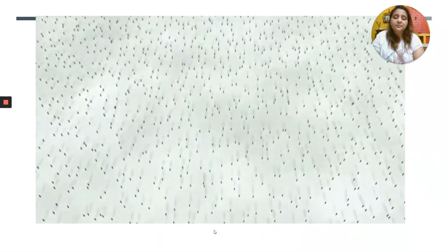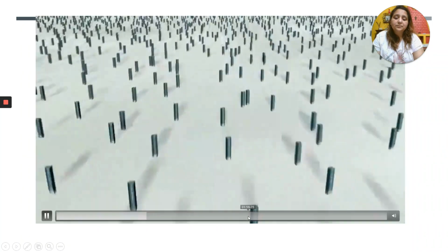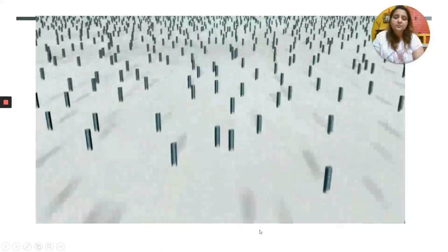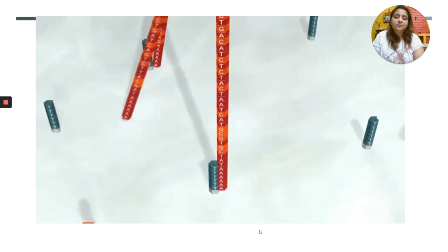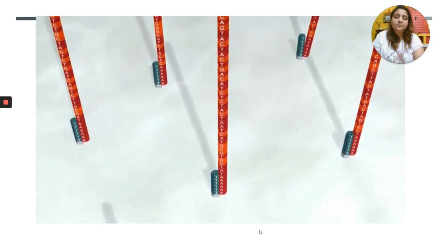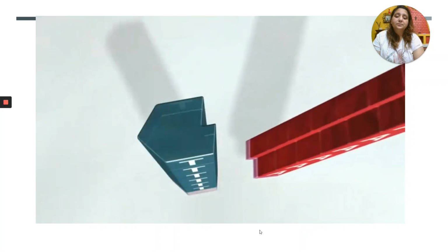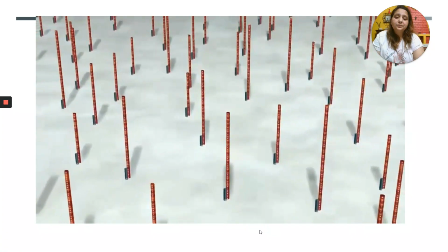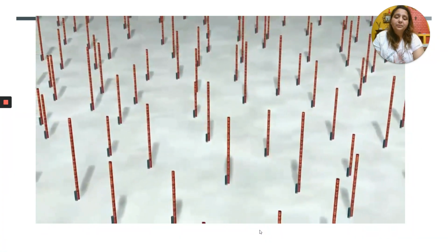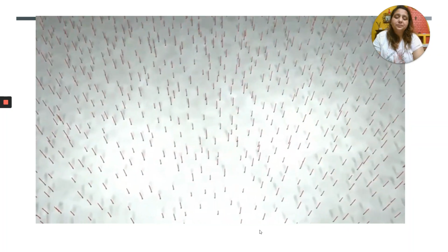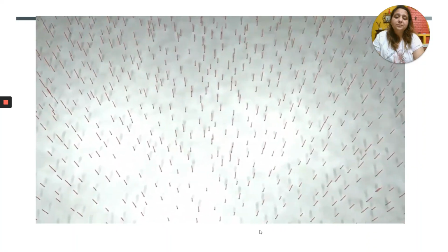The DNA strands are then hybridized to the flow cell, which contains billions of oligo-T universal capture sites that are immobilized onto the flow cell surface. Each individual template that hybridizes to the flow cell surface will generate its own sequencing reaction. Because the Helicos sequencer detects single molecules, the templates can be mapped at a very high density of over 100 million templates per square centimeter.